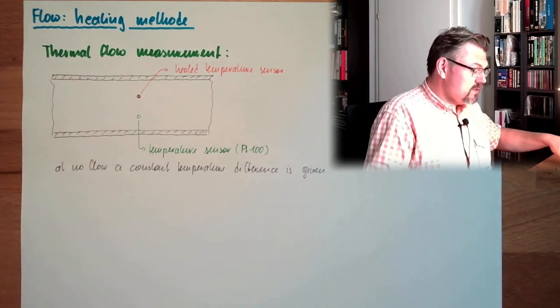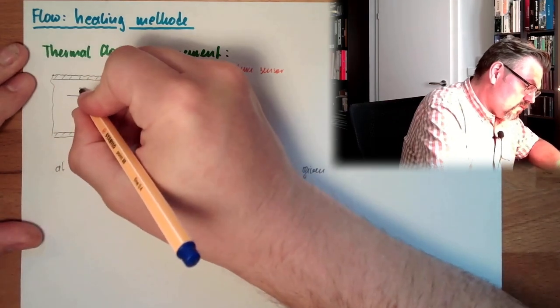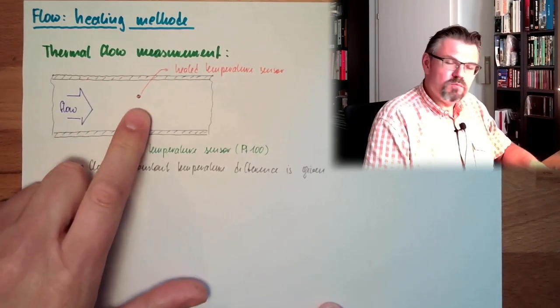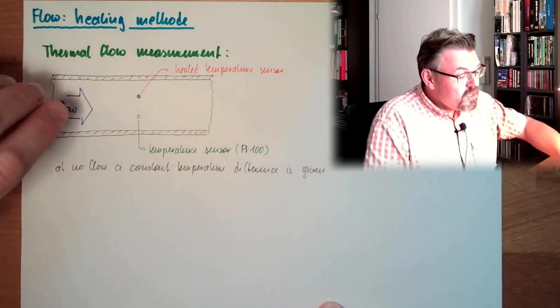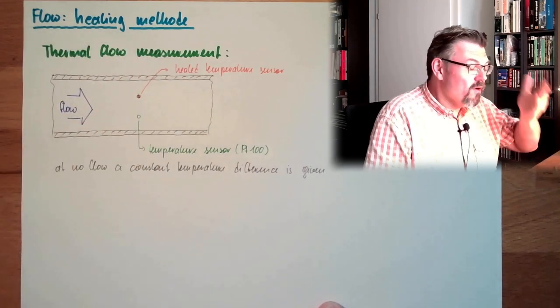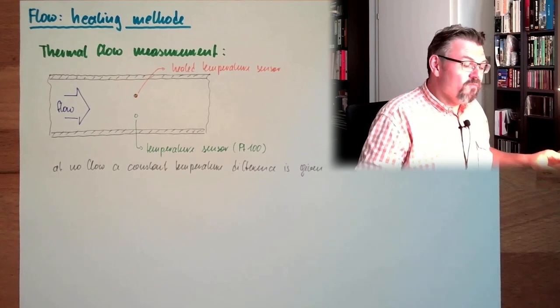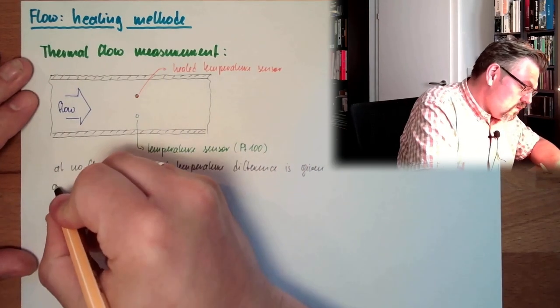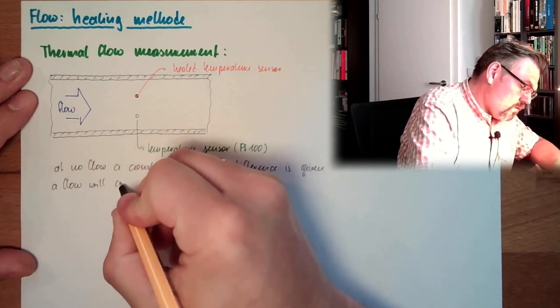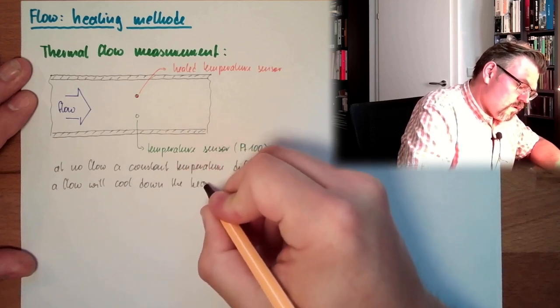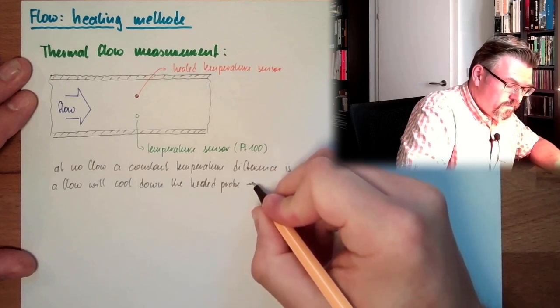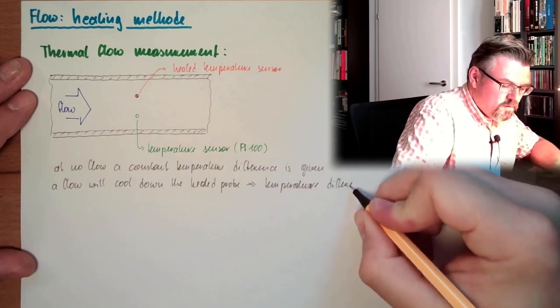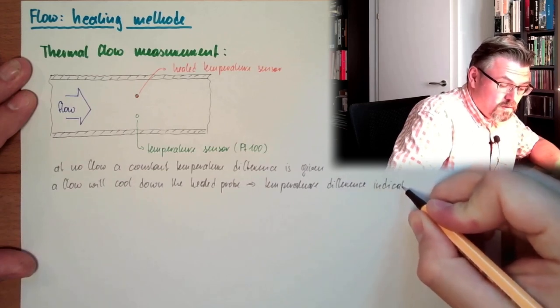Now if the flow starts, the direction of the flow doesn't really matter. So here we have the flow. The flow will cool down this probe. It's heated, but since the flow is streaming around this heated temperature probe, this heated temperature sensor, this is cooled down by the medium. So a flow will cool down the heated probe. Temperature difference indicates flow speed.